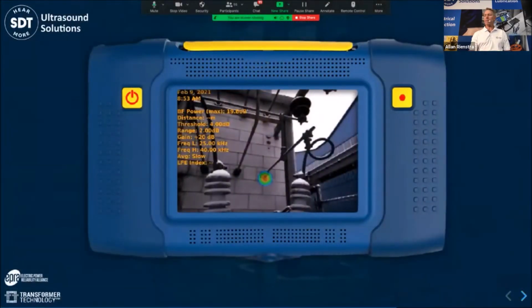So when we froze this and took a picture, what Craig found was that there was a partial discharge occurring right at this termination point, right at the brick wall here. He said it's quite common—he finds a lot of situations anywhere you're moving through a wall like that, because the buildings resonate and vibrate, and over time that breaks down the insulation, and you get partial discharge there.